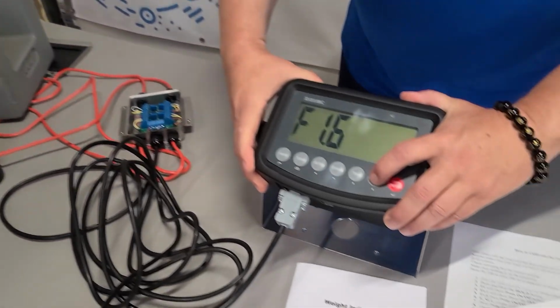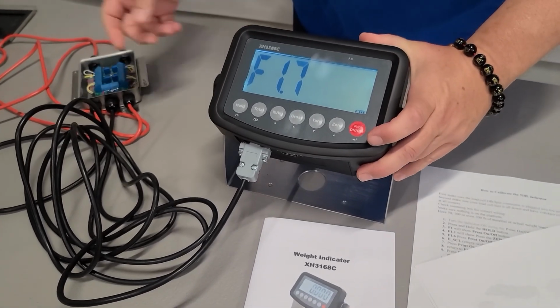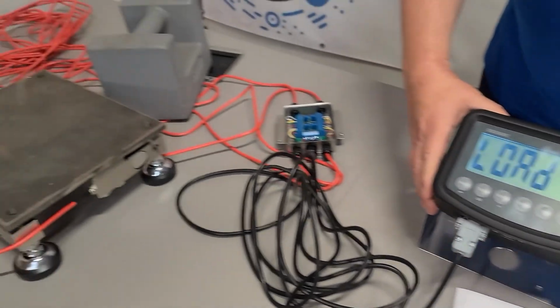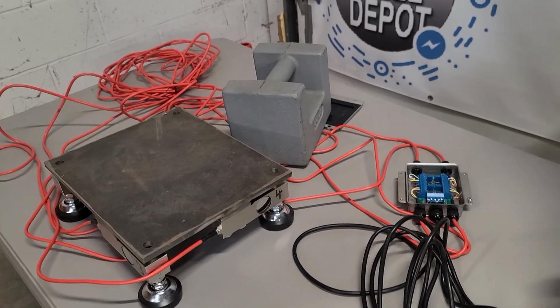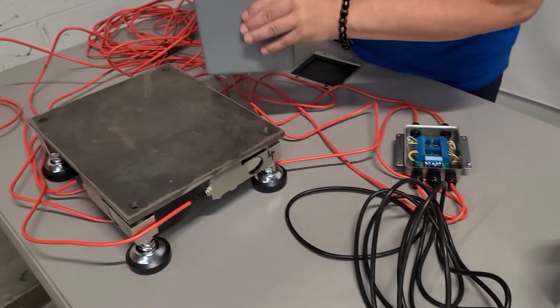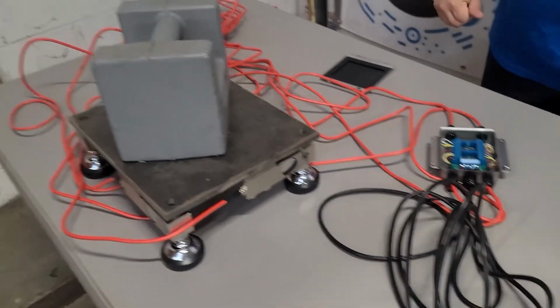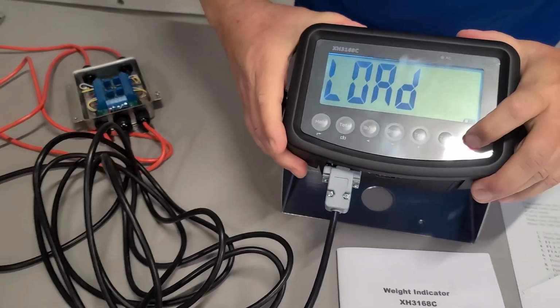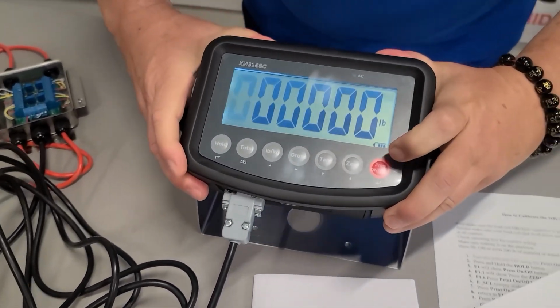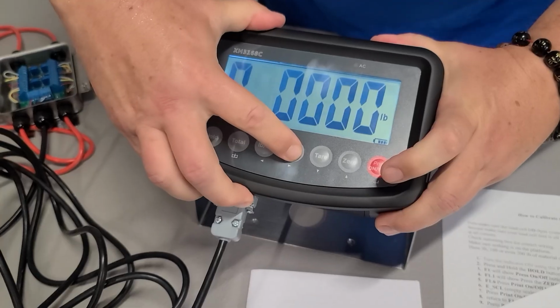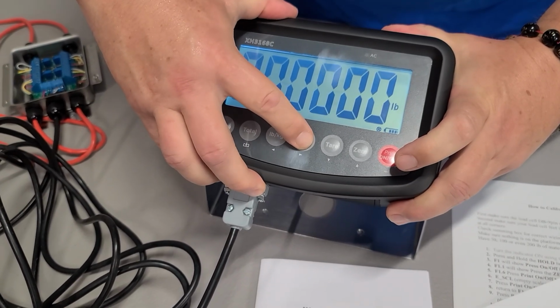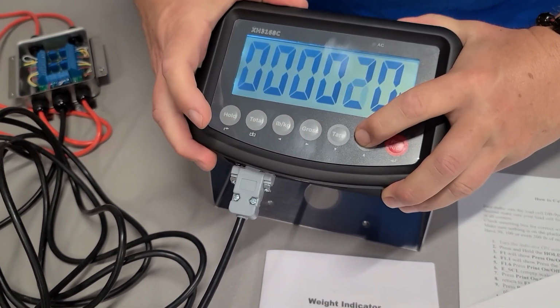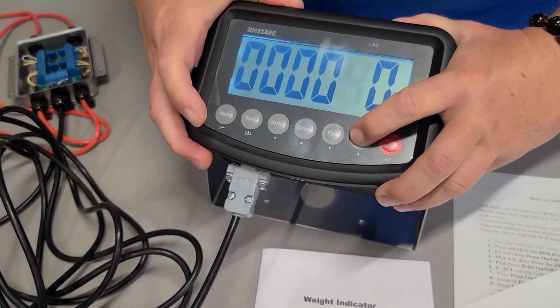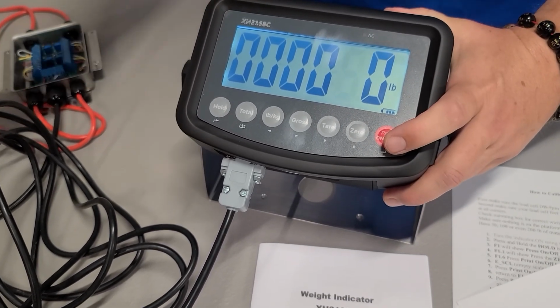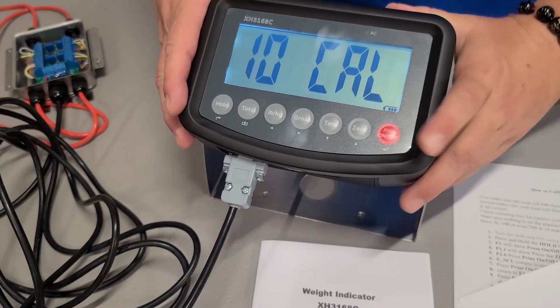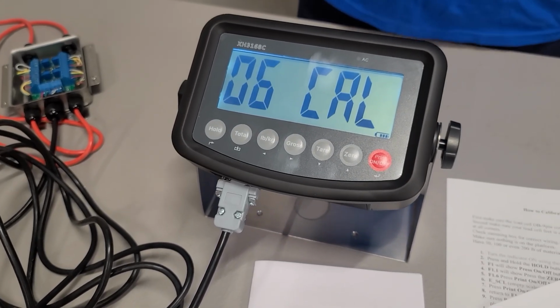Then you can go to F7, which is your span calibration, the reason I brought the weight over. It tells you to load the weight. So whatever you have, you put it on your platform. Then you tell the indicator how much you put on. Right now, we put on 50 pounds. The weight is on it, 50 pounds entered. Now it's going to count down again.